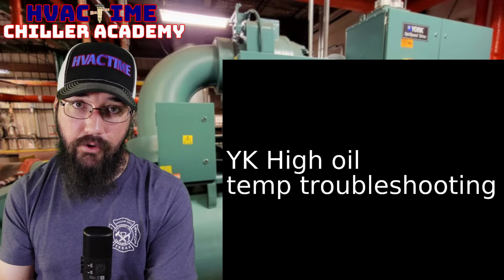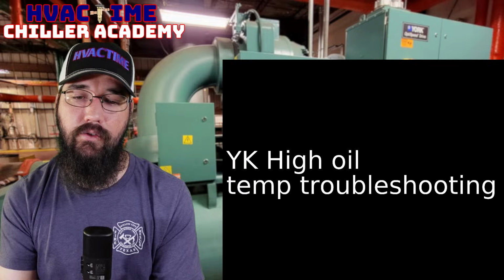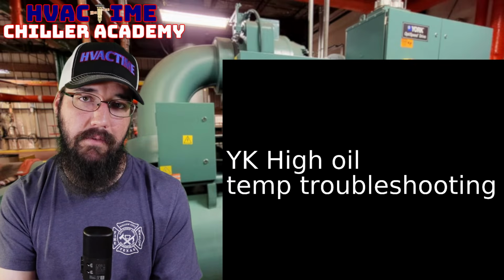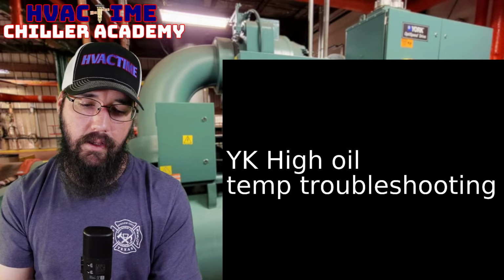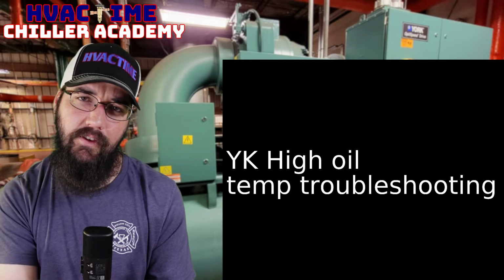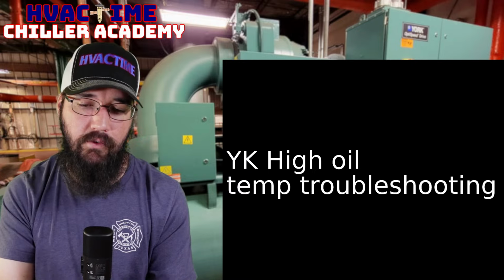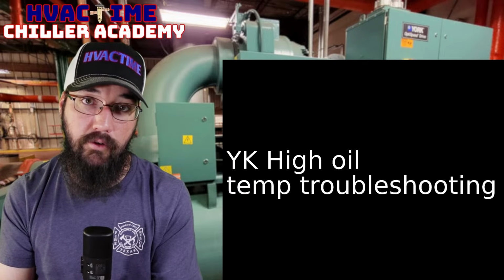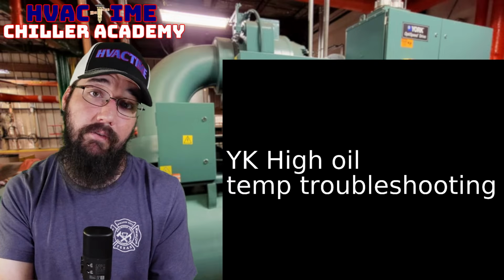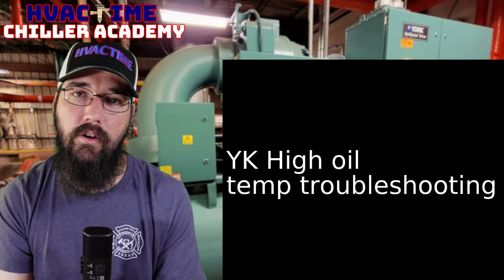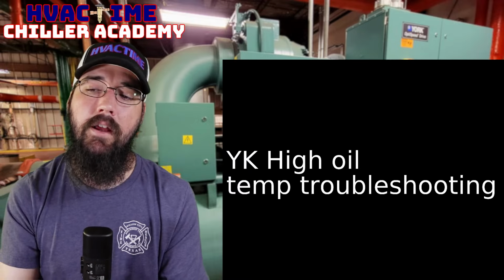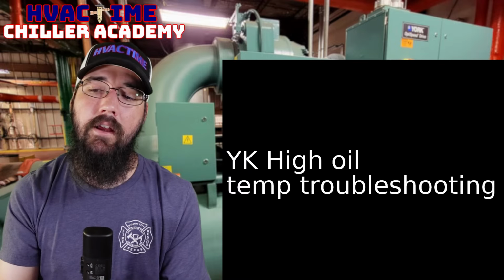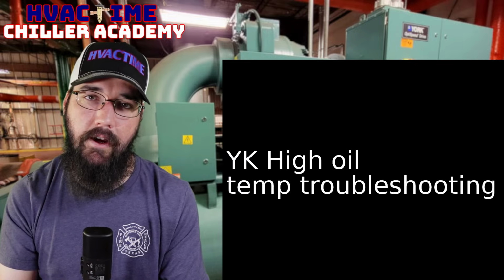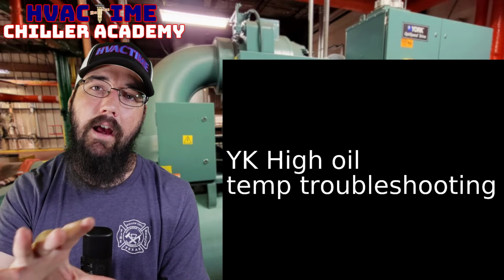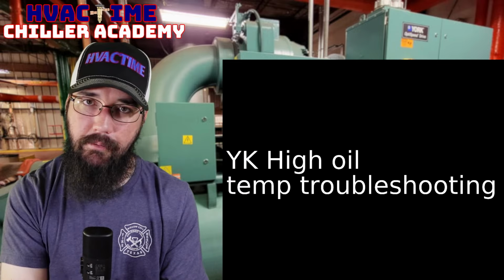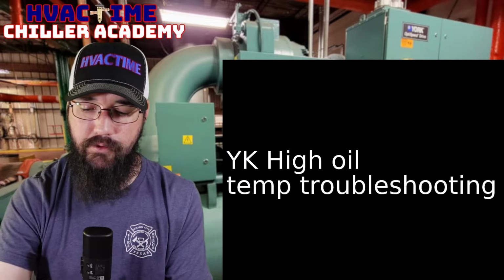If those are good, then we can take the time to dive into the oil cooler as my next, kind of final step, if you will. Where's the oil cooler and its metering valve and all that stuff, because that takes more time and gets more complex. If you spend all this time troubleshooting the oil cooler first and it's really just an oil temperature sensor issue you never verified, or your oil heater is constantly on all the time, then you miss the really easy thing to go for the hard thing, right? So that's why I want to start with the other stuff first, get all that resolved, then put time into that oil cooler. That's my personal troubleshooting process there.